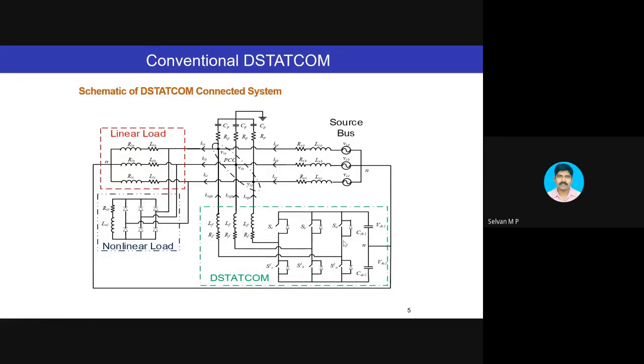So now this is a STATCOM voltage source inverter based on IGBT switches or GTO. That's why nothing is mentioned here. A switch is shown. So by operating this, I will be able to inject reactive power or absorb reactive power in the system. If I inject reactive power, the power factor at this point will be improved. Of course, I can do this with the help of a capacitor. As I said, a capacitor will be able to provide compensation, a fixed value of reactive power, and it can provide the required reactive power only when the voltage is at rated voltage.